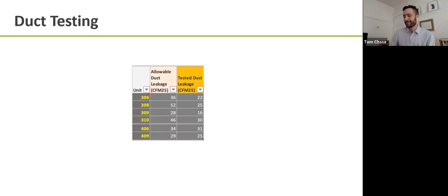This was a really exemplary project. We find that duct testing reveals a whole lot of surprises down the line, often in places you don't want to see them. Peterson Engineering does great details around duct tightness testing in their drawings, and we had a contractor on this team that really understood those and carried them through. We passed every duct tightness test on the first try, which was remarkable, especially given leaky boxes and leaky fan coil units from the manufacturer—those were all sealed up and made our job easy here.